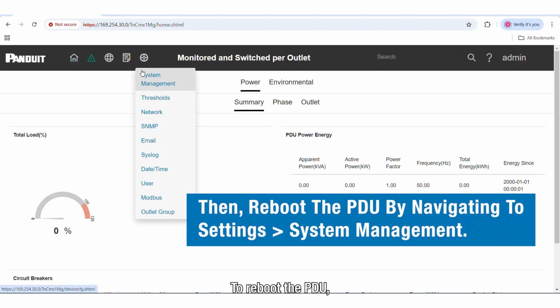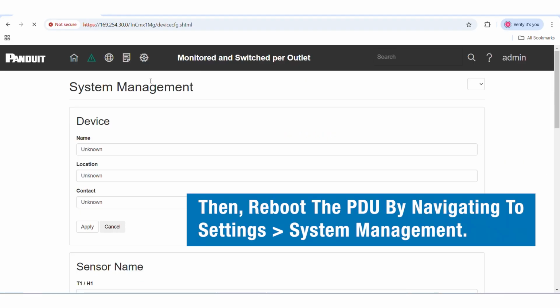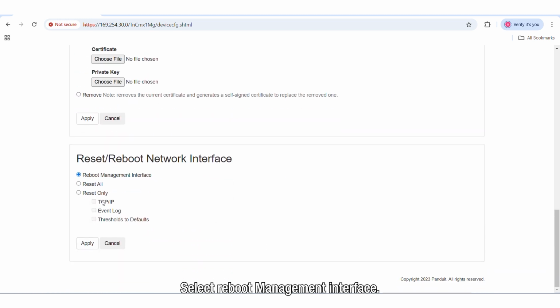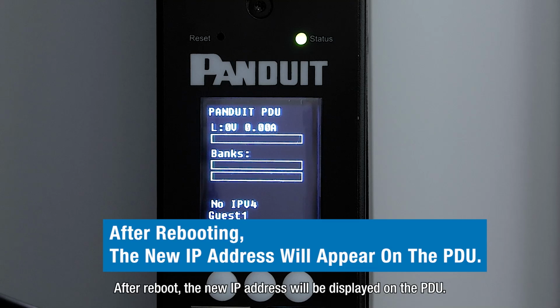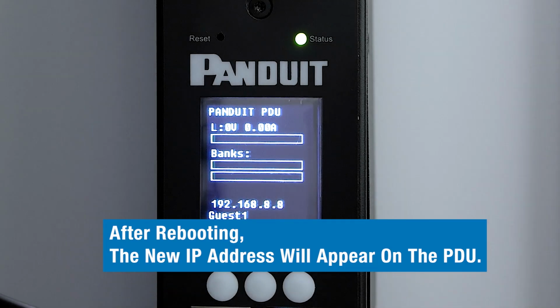To reboot the PDU, navigate to Settings, System Management. Scroll down, select Reboot Management Interface, click Apply, and wait for the system to restart. After reboot, the new IP address will be displayed on the PDU.